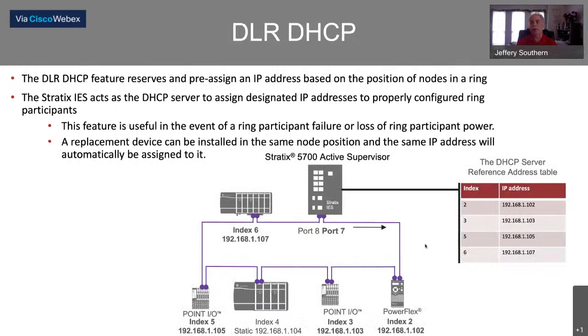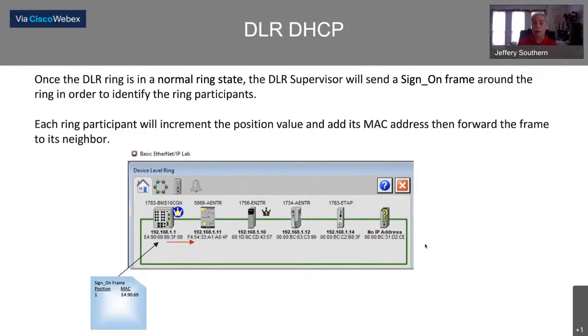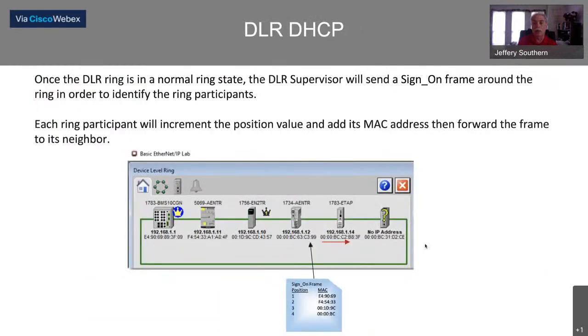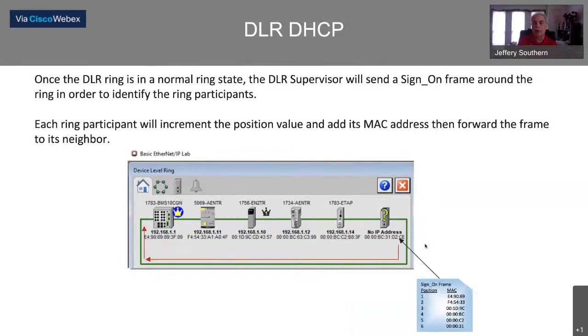One of the last things on DLR is DHCP. In the past, we couldn't set the IP address in a DLR ring, but now with the 5700 it can act as a DHCP server and assign IP addresses by position in the ring. So if something's missing, it can get its IP address by knowing which one's missing and giving it the correct address.